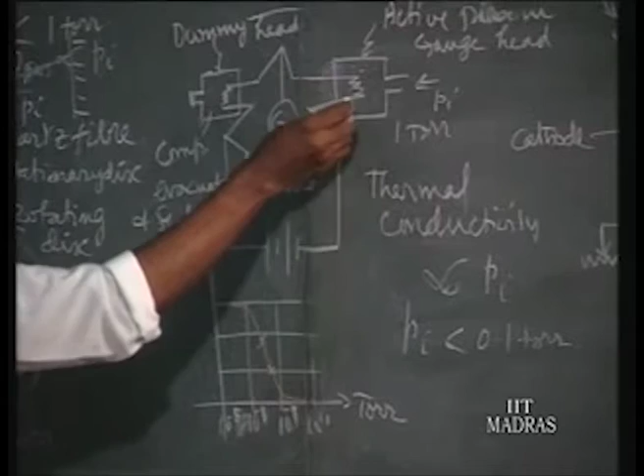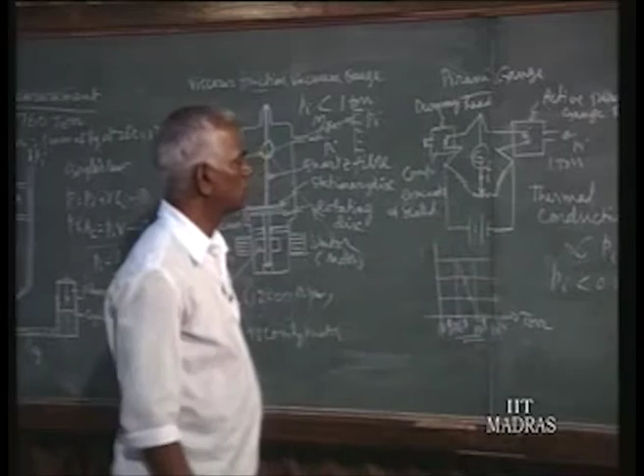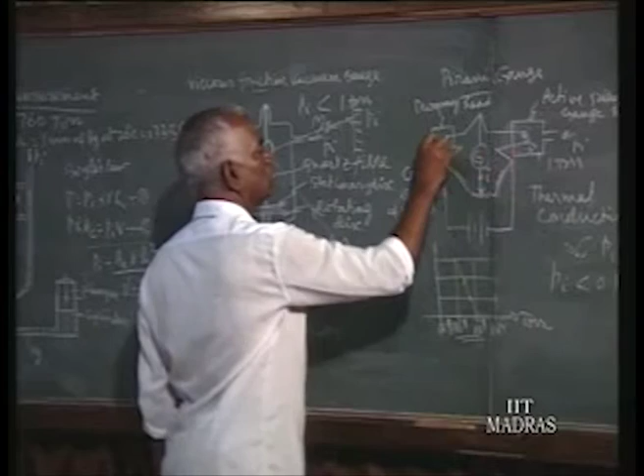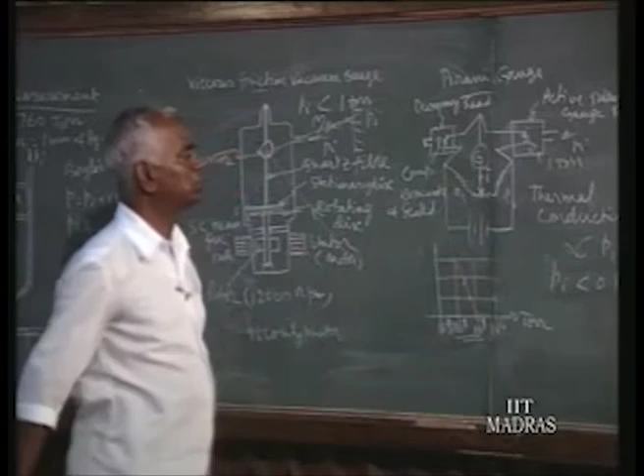So as the vacuum is increased, the imbalance increases because resistance keeps on increasing, though current is decreasing. This is the calibration curve. Later on, for the same gas, unknown vacuum pressure can be found out by this. So the arrangement of the circuit is like this. It forms one of the arms of the Wheatstone bridge, with a dummy head in the adjacent arm. These are all constant resistances, call them R1, R2, R3, R4. This is for initial balancing of the bridge for calibration purposes.